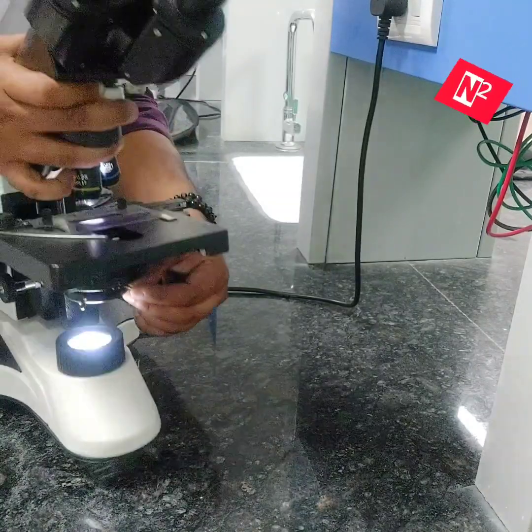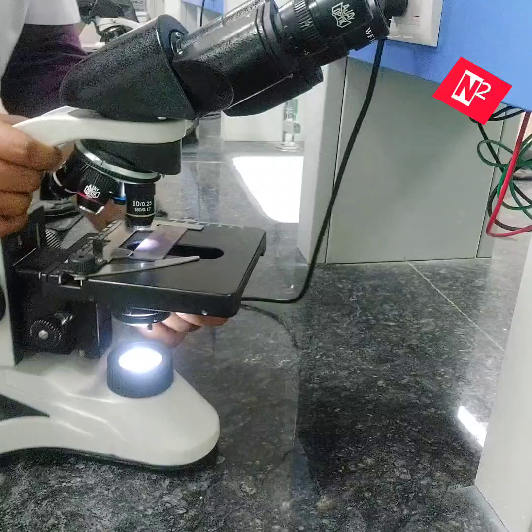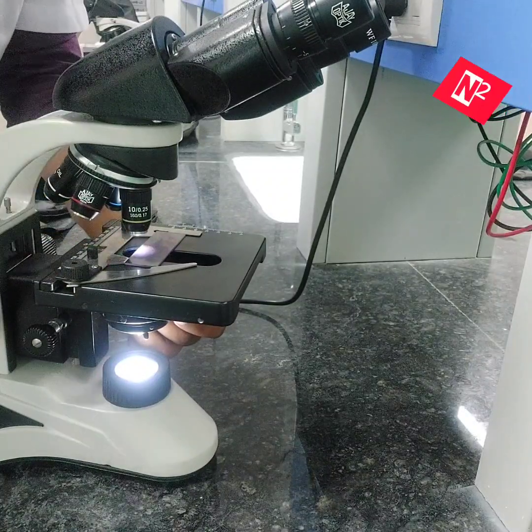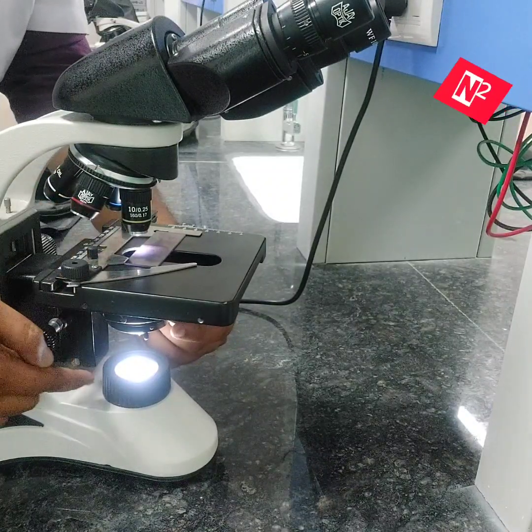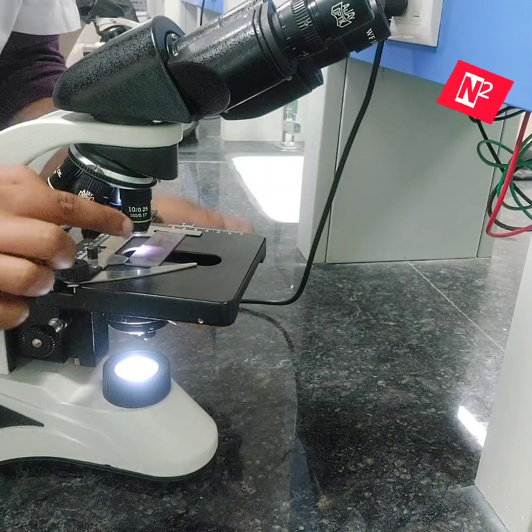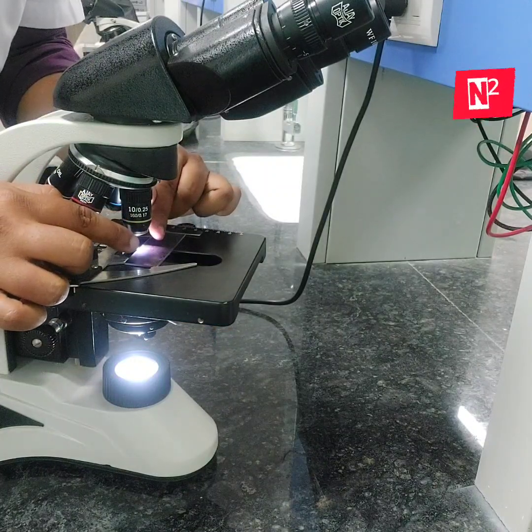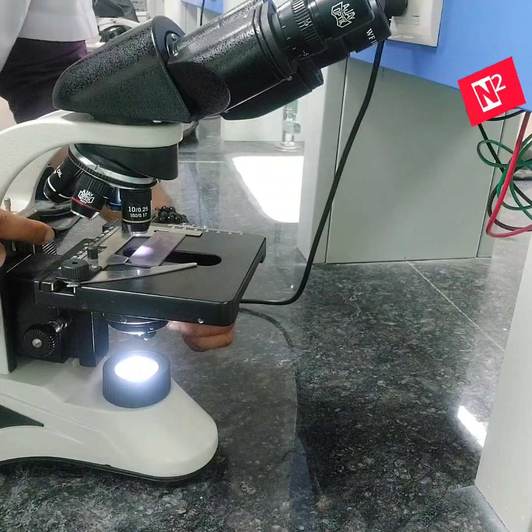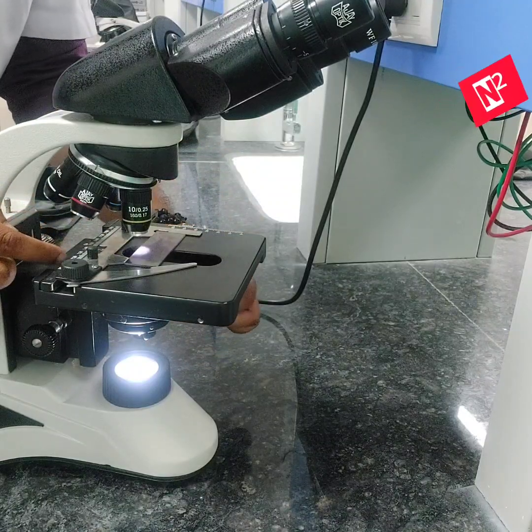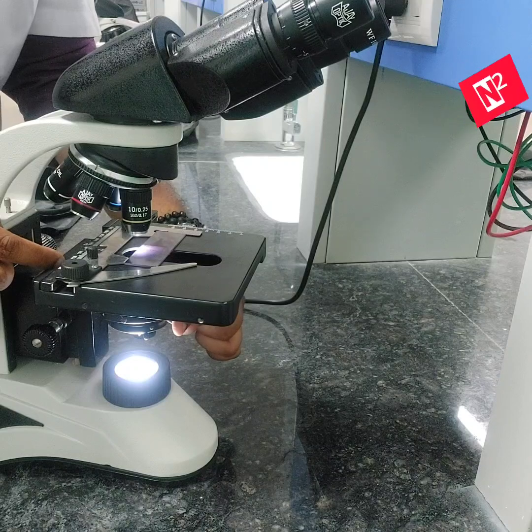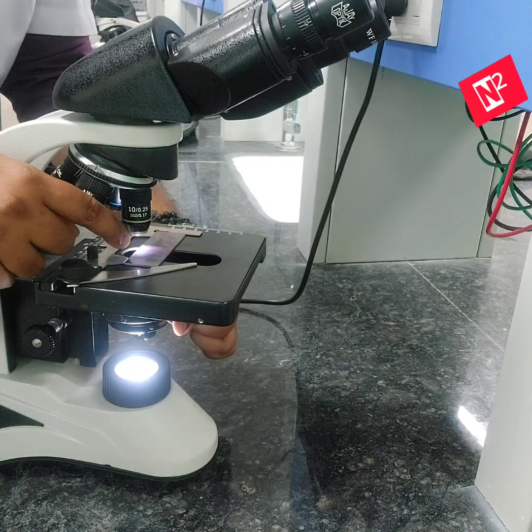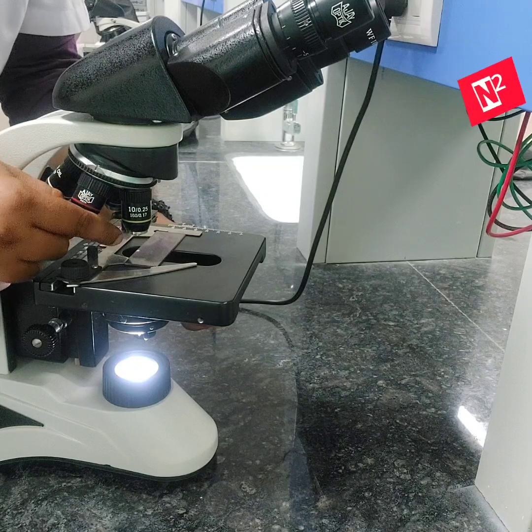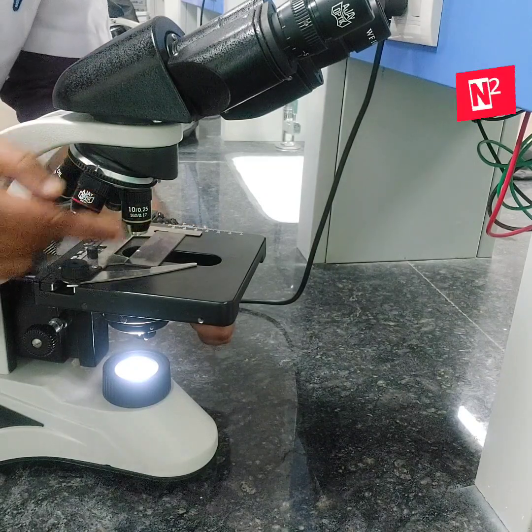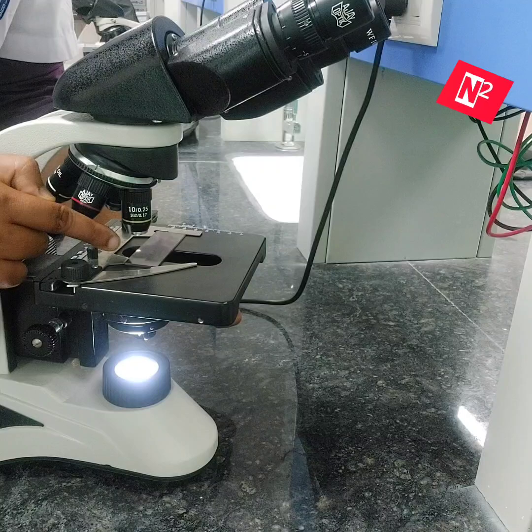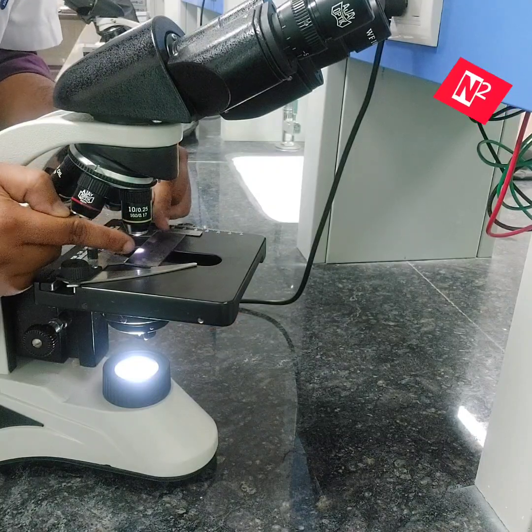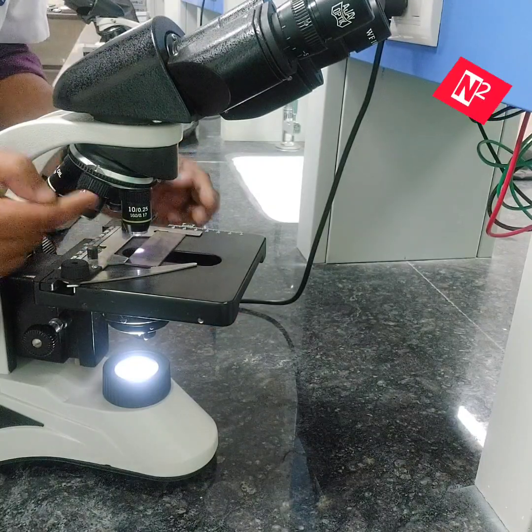How do you know at what point it is opening or not? Observe the top part of the stage: the light is emitted from the artificial source, passes through the condenser diaphragm system, then passes through the central aperture of the stage. When I regulate the light, see, now I have completely opened the diaphragm, and the stage is completely illuminated. Now I have completely closed it. So when you are using 4x, the condenser should be at the bottommost position and the lever should be partially open, so that a kind of pinhole light appears from the center of the stage.